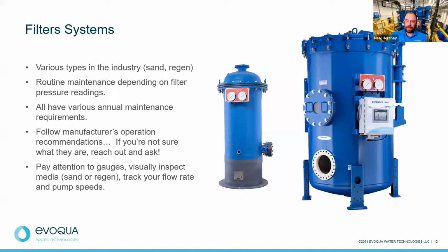So, going back to that tracking of your mechanical room and keeping records, you're going to see that different systems probably have different loading and different time frames for all this maintenance. So that's important to build into your plan as well, and realize that not everything is going to move at the same pace. So tracking things like your flow rate and pump speeds all comes back together to give you an idea of timing and make sure all your equipment's running at peak performance based on the loading in that particular pool.